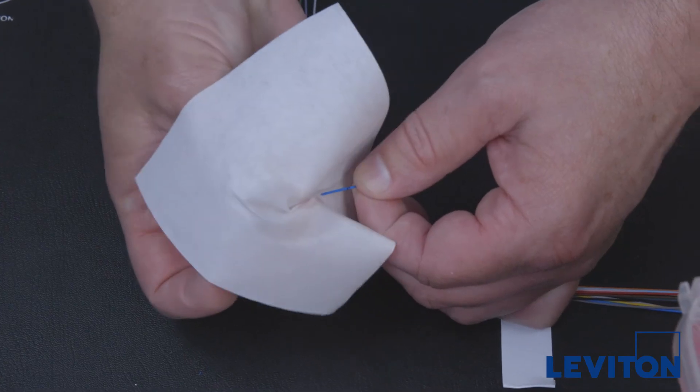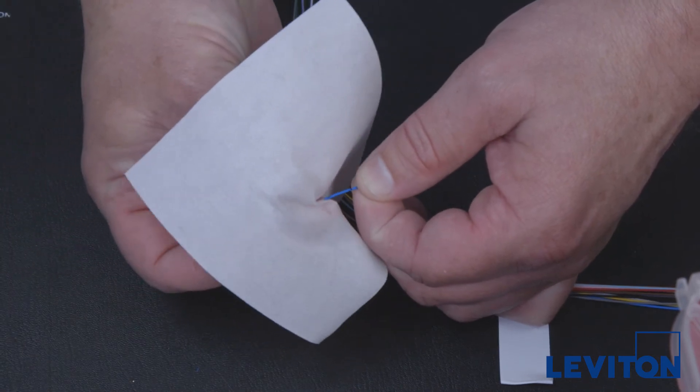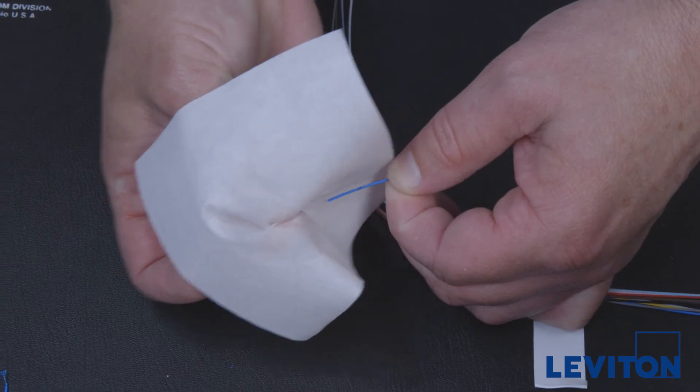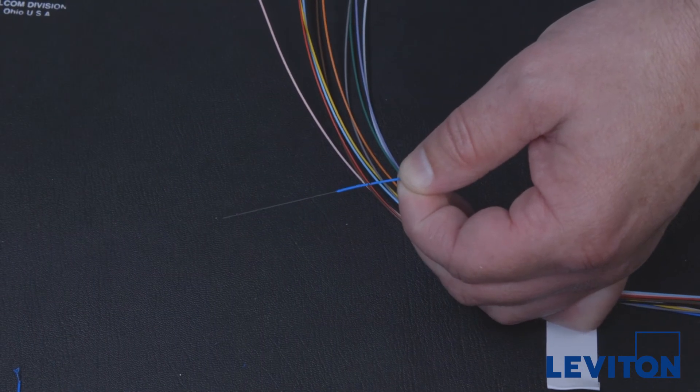Clean the bare fiber with an alcohol wipe to remove any debris. You will hear a squeak when cleaning. If no squeak is heard, recheck the fiber to ensure the acrylate coating has been removed.